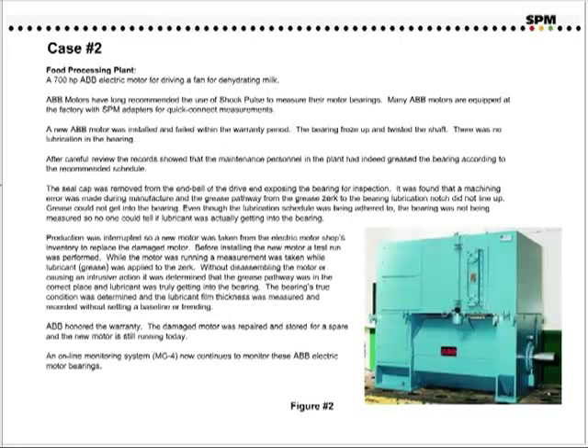Case number two. This is a food processing plant, and the application is a 700 horsepower ABB electric motor for driving a fan for dehydrating milk. ABB motors have long recommended the use of Shock Pulse to measure their motor bearings. Many ABB motors are equipped at the factory with SPM adapters for quick connect measurements. In this case, a new ABB motor was installed and it failed within the warranty period. The bearing froze up and twisted the shaft.